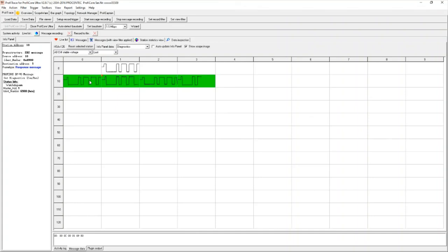There's a very useful button called 'Show Scope Image' — when you click it, it gives you a snapshot of the physical signal of each specific device. This is a very nice quick overview way to check if there are any problems in the segment. For example, removing a termination immediately affects device 12's scope image. Shorting the network affects almost everybody. When I click on a device, it updates me on the physical state in a panel on the left. A red flashing light on device 12 indicates extended diagnostics — in this case, a redundant power supply on one of my devices is not connected.